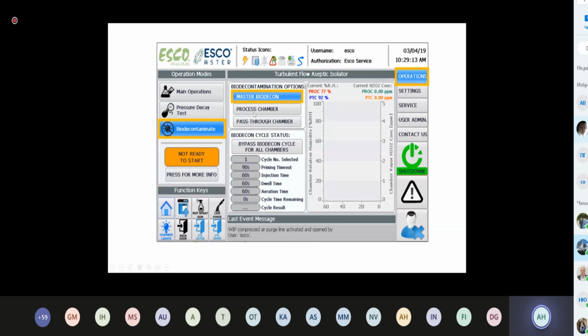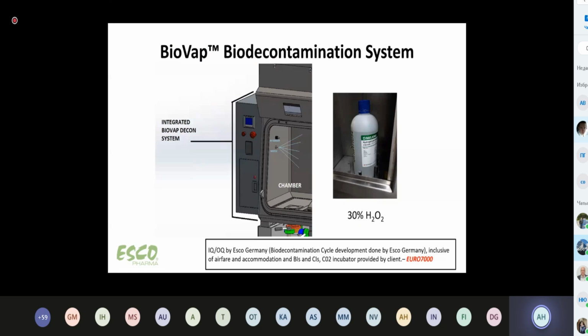Everything, one by one. And if you look here, please ignore the time. This here is called a cycle. So for every batch, as I told you before, these numbers, it can be one cycle, number 1. Maybe here will be 5 minutes, here will be 10 minutes, here will be 20 minutes, something like that. One cycle here to develop this and to verify the result is 4,000 euro. 4,000 euro, one cycle. This is called one cycle. You can have several cycles depending on your batch. Okay. And I say the batch depends on the amount of items you put inside. Okay. So the principle is very simple. You have a bottle of H2O2, 30%. This bottle sits on a load cell, a weight sensor.